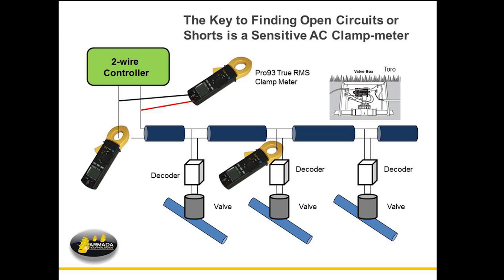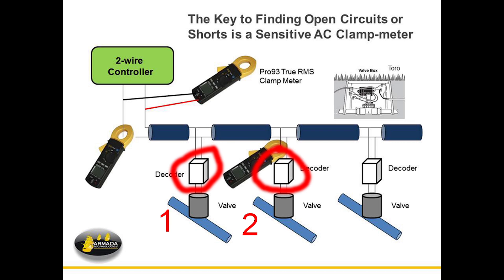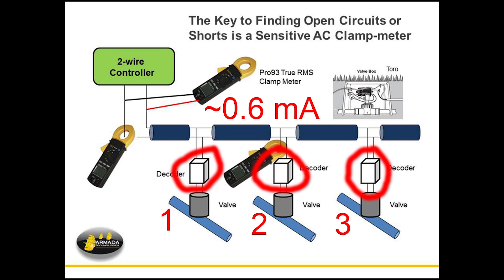Then you see a series of decoders here. In this case, we have three of them, but the system will continue on down. Typically, a decoder will draw 0.6 milliamps per decoder, but specs will change based on manufacturer. It might be higher or could be a whole lot lower.